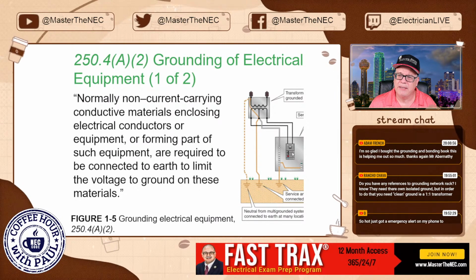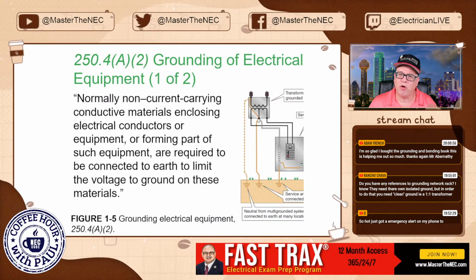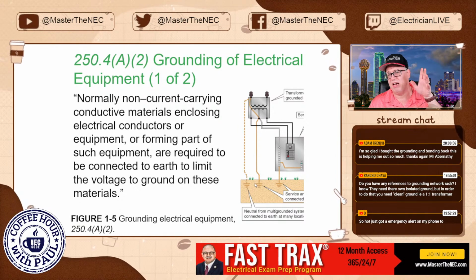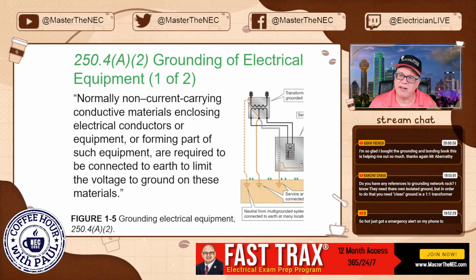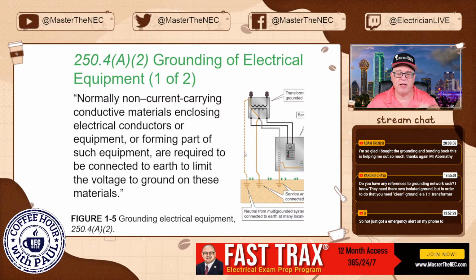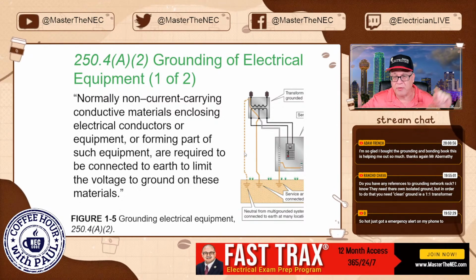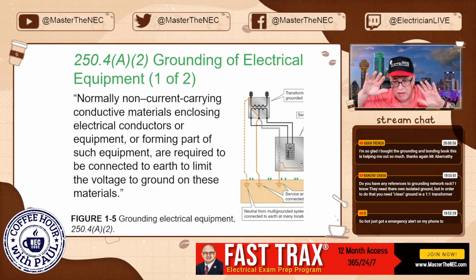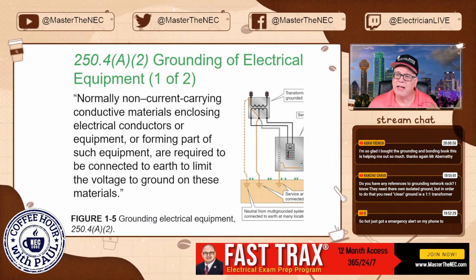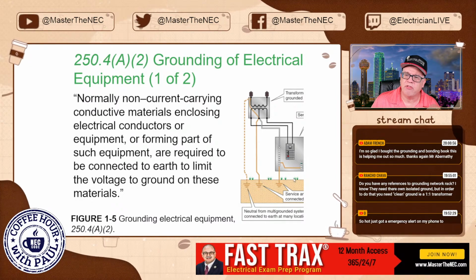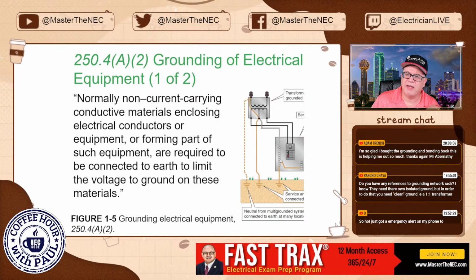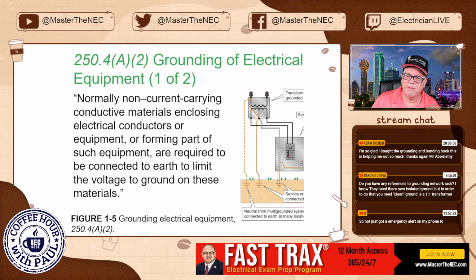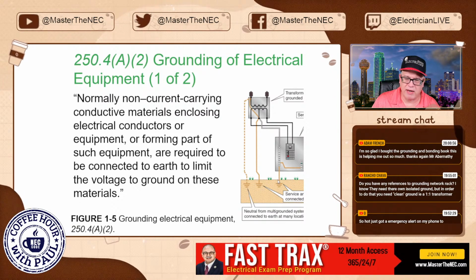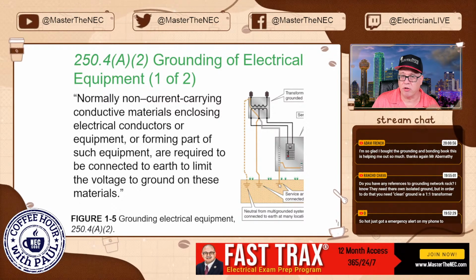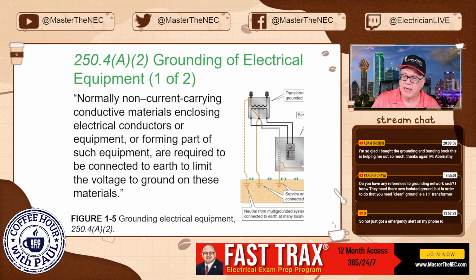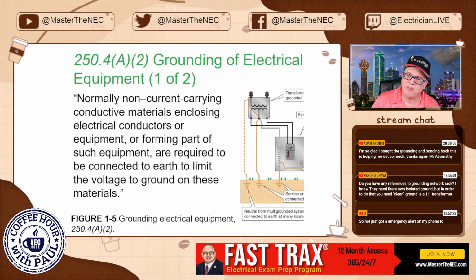This is your house. And here the transformer has a connection to earth out at the transformer. And this dashed line is depicting that there are other nodes on the system that are connected to earth, because that's called a multi-grounded system, multiple points. And then here's our service. So in our service, you've got your grounding electrode conductor, which we have to have. We have to have the grounding electrode conductor going to an electrode. And you'll notice that this conductor right here, this is the main bonding jumper.